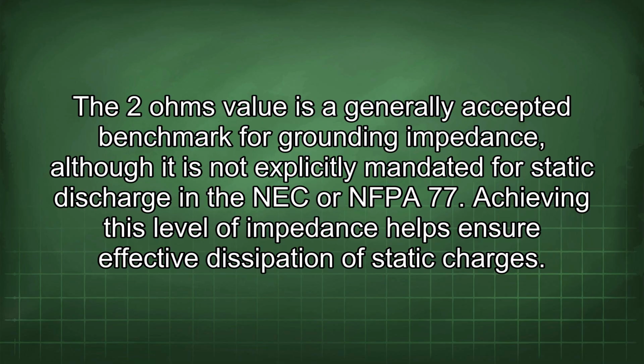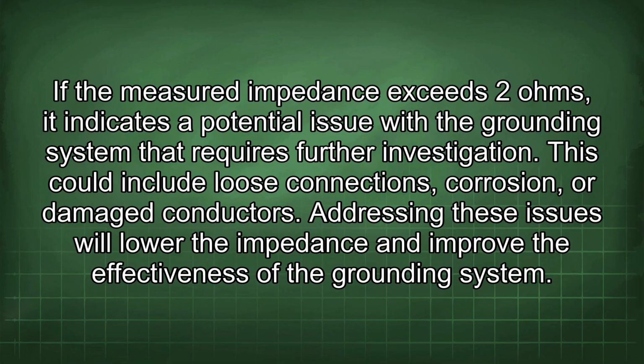The 2 ohms value is a generally accepted benchmark for grounding impedance, although it is not explicitly mandated for static discharge in the NEC or NFPA 77. Achieving this level of impedance helps ensure effective dissipation of static charges. If the measured impedance exceeds 2 ohms, it indicates a potential issue with the grounding system that requires further investigation. This could include loose connections, corrosion, or damaged conductors. Addressing these issues will lower the impedance and improve the effectiveness of the grounding system.